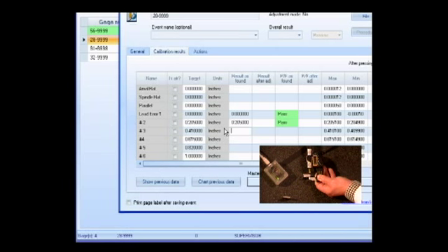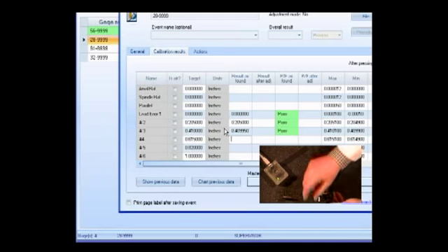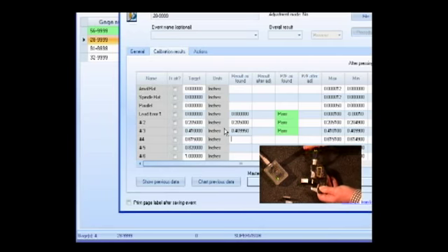Right. Now this gauge has been used quite a bit. We love this micrometer. It's one of ours that we really like. Well, we noticed around the half inch range and higher, it's starting to wear. And you'll see this on this event. Now instead of 410, it's 409.95. It's still well within tolerance. It's allowed us out a tenth. It's only running 50 millionths, but it is wearing. It's showing some wear, and that would show up on those stability trends, linearity trends, wear analysis. It shows up on all the different charts.